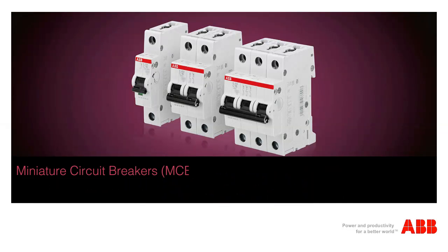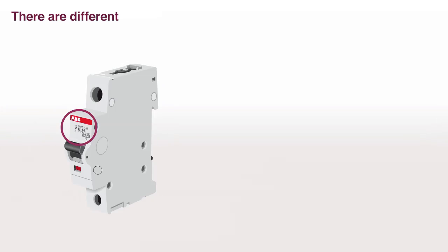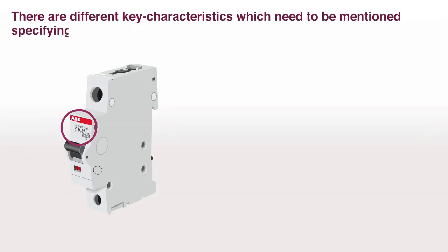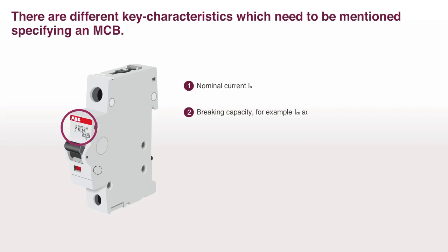Miniature circuit breaker, MCB, specification. There are different key characteristics which need to be mentioned when specifying an MCB. Nominal current, IN. Breaking capacity, for example ICN according to IEC EN 60898-1.